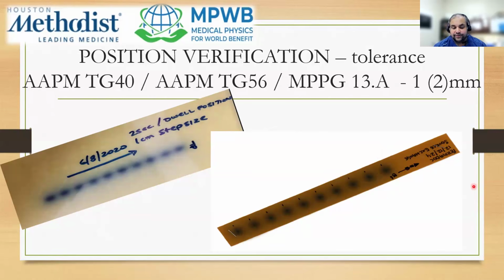Now, at least with the Bravos, they also have a CamScale device that does your position verification test at 150 cm, 120 cm, and 90 cm. I know the Elekta afterloader also has a ruler, and you can do a visual check of your position verification test. So this is very important to do, especially before the engineer heads out after the source exchange.